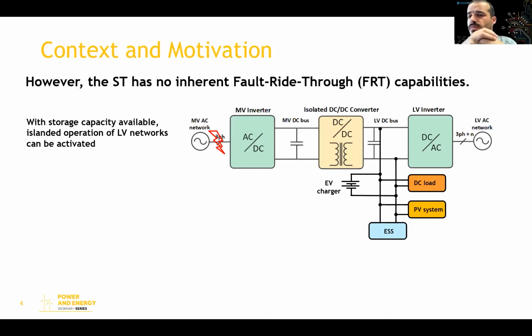However, the smart transformer is a power electronic device, and because of that, it has no inherent fault ride-through capabilities, which is something that the traditional low-frequency transformer doesn't have concerns about. So we need to develop advanced functionalities to provide these capabilities to the smart transformer. We know that if we integrate storage with the smart transformer, we can simply island the distribution networks, and the fault ride-through capability may not be a big deal.